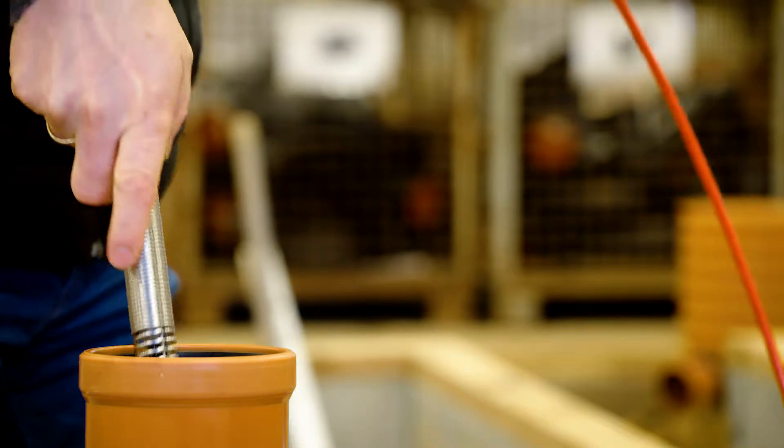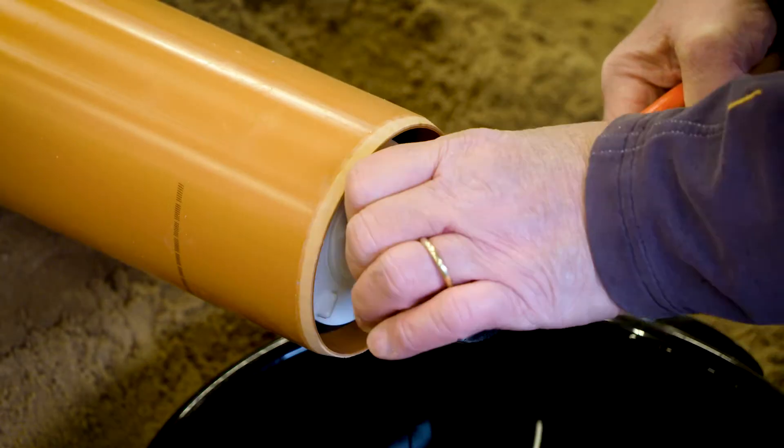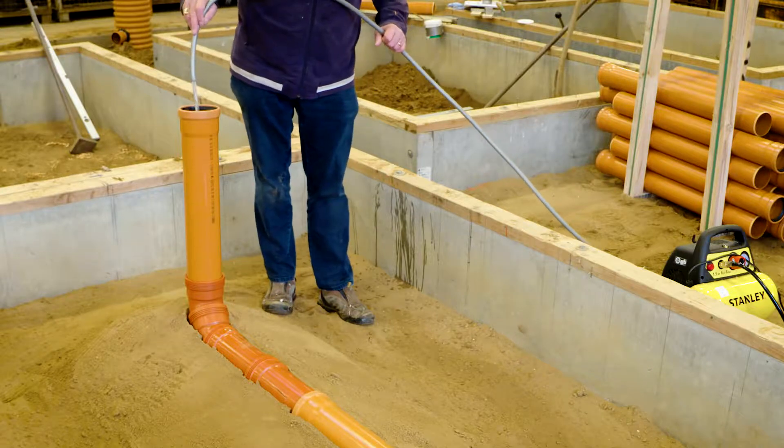Insert the inspection camera into the leaky sewer pipe. This is how the leak looks from the inside. Block off the cleaned pipe with a multi-seal test plug and fill the pipe section with water to determine the water loss.